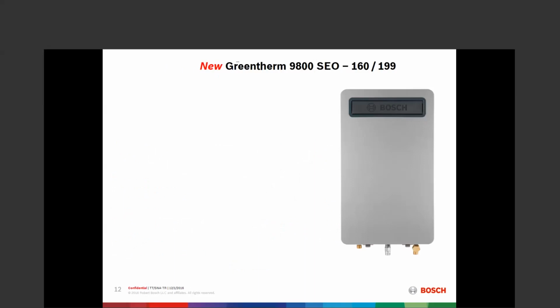And it looks like this. The vent for this outdoor unit is actually this channel around the Bosch logo here. That's the vent all the way around there. And the air intake is on the back of the cabinet, a series of louvers on the back of the cabinet. All the connections are on the bottom, including the water. Obviously, with an outdoor unit, you really don't want top connections.